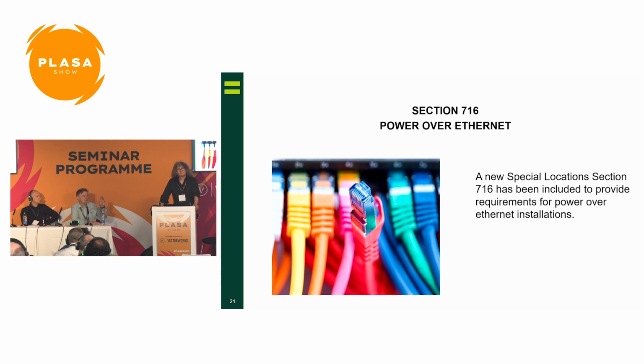The special location also refers people to the telecoms installation standards for cable management, because with high data rates now, there are particular requirements about things like how tight the bend radii should be for the cables and how you should strap them down - not tight with a nylon tie, but with Velcro ties and things like that. But that's a completely different standard to this.